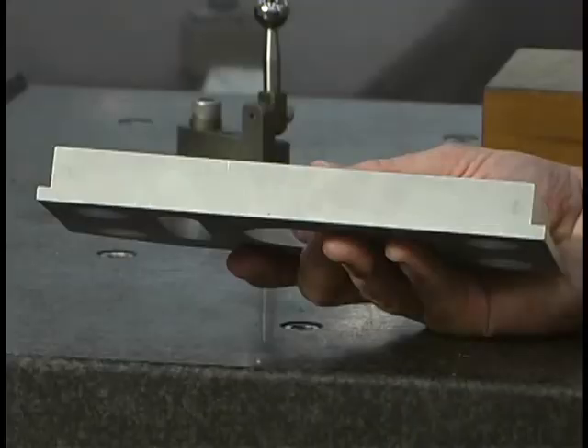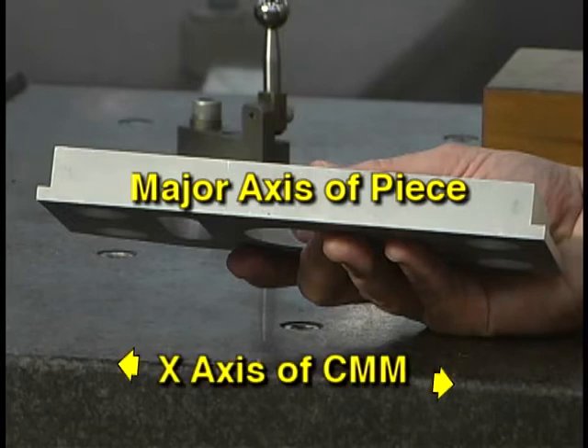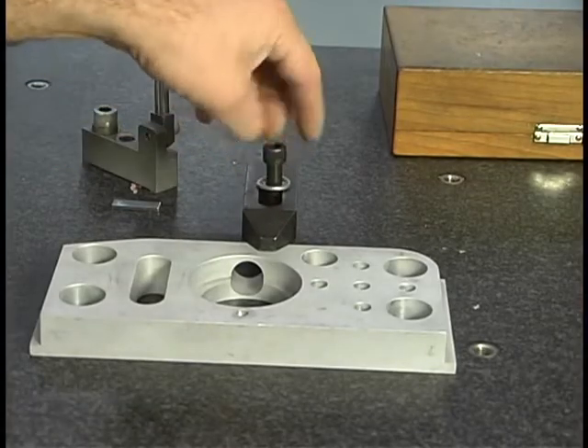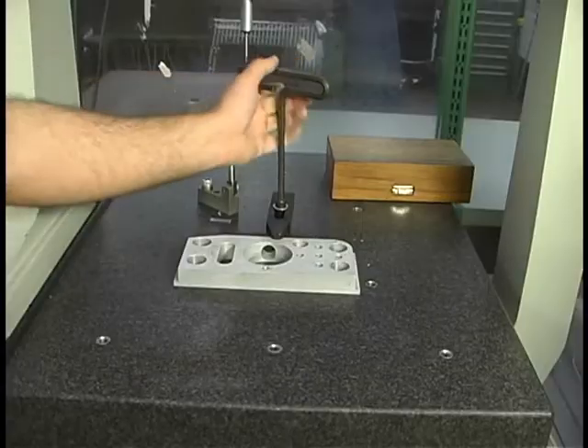Try to align the major axis of the workpiece with a major axis of movement of the CMM. In this example, the major axis of the part is aligned with the x-axis of the CMM. Place a clamp and set its height to the proper level to hold the workpiece firmly down against the surface plate. Snug the clamp with the proper wrench.